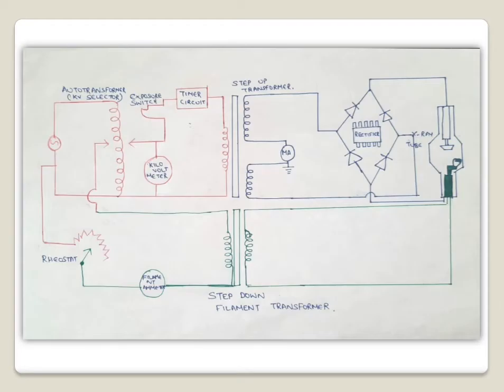The third circuit is the filament circuit. In the filament circuit you will find a rheostat and a step-down transformer, known as the filament transformer. The function of the filament transformer is to supply power to the cathode filament so as to produce heating of the cathode filament and thereby facilitate thermionic emission for producing electrons.